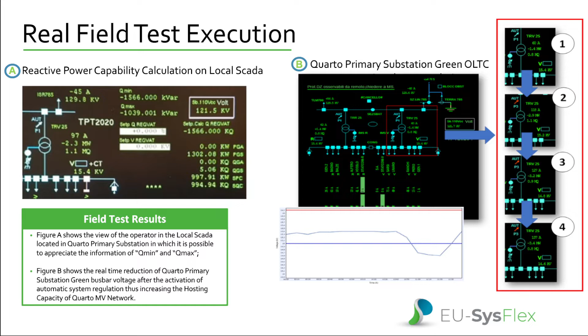Thanks. So we can see how the regulation has been activated also for the PV generators participating in the regulation. In particular, we can see an increasing of reactive power and also a decreasing of the active power during the test for the group of Quarto FTB and the two groups of SANA 1 and 2, which regulated during the test the reactive power. It is important to specify that this measurement is averaged every 10 minutes, so it is possible to lose some significant point during the regulation, but during this time window it is possible to appreciate also a variation in terms of voltage.